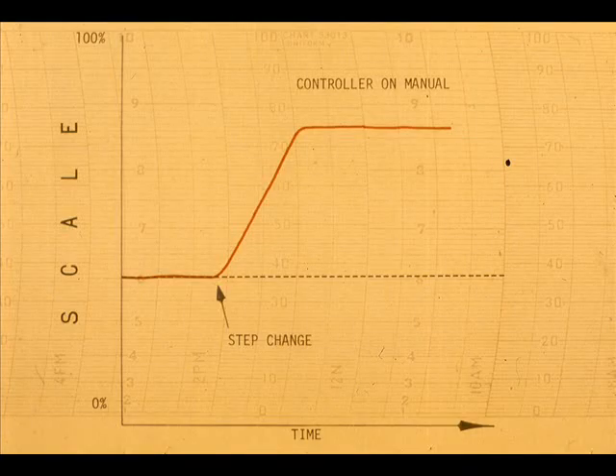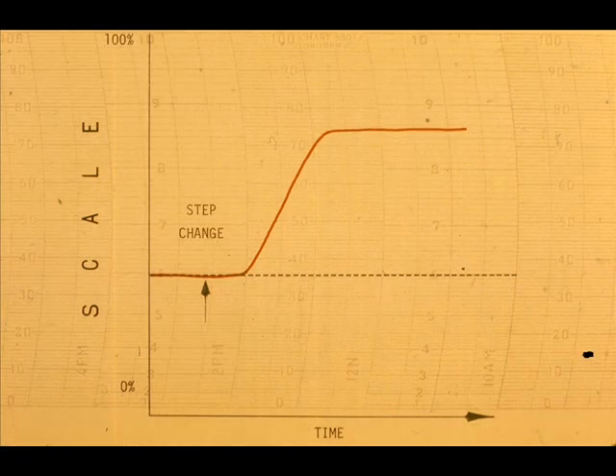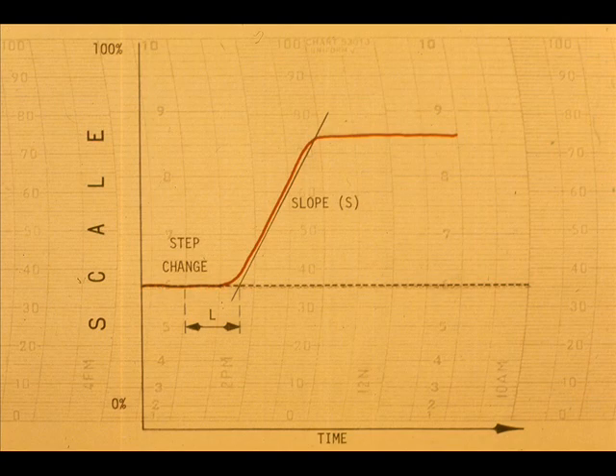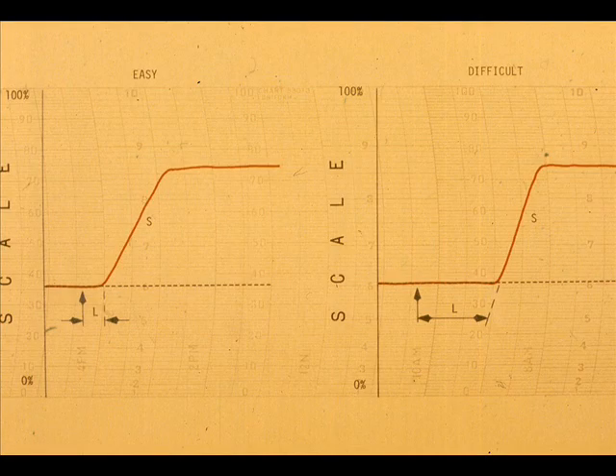The process may make an immediate response after the step change, or the response may be delayed by lags and dead time in the process. The time L it takes the curve to reach the most rapid rate of change, multiplied by the slope S, determines the controllability of the process. The higher the product of S times L, the more difficult the process is to control.